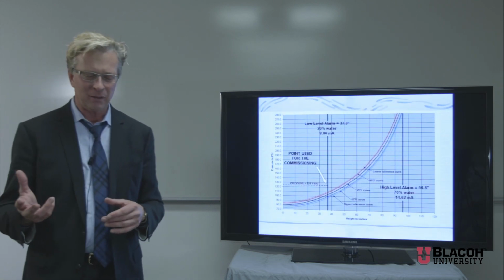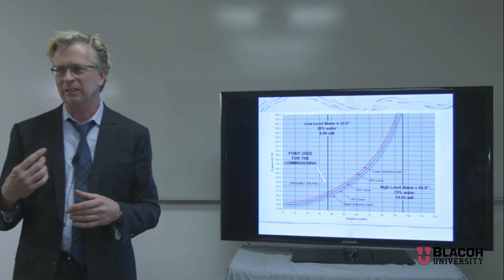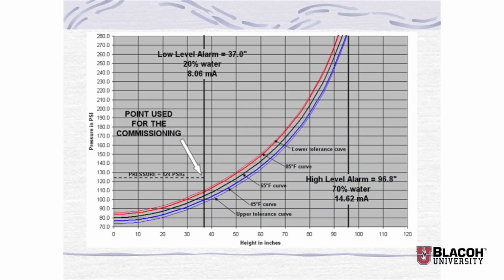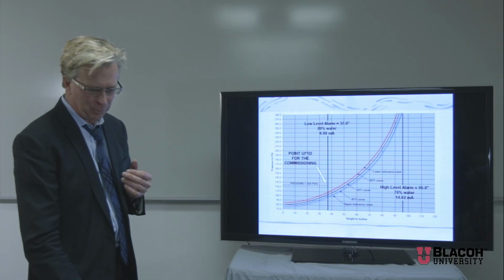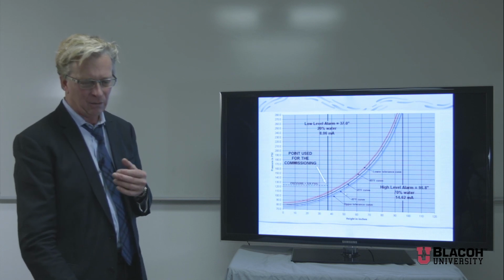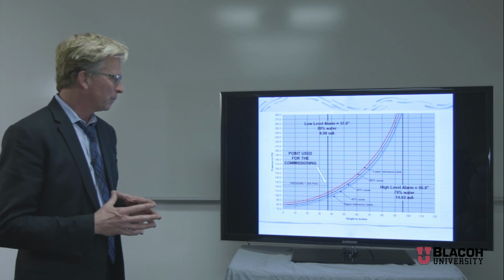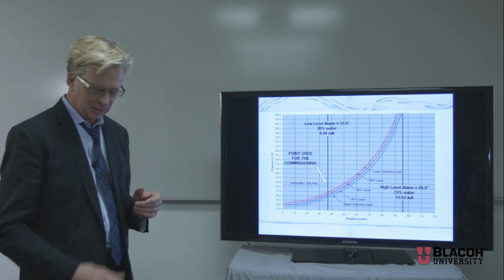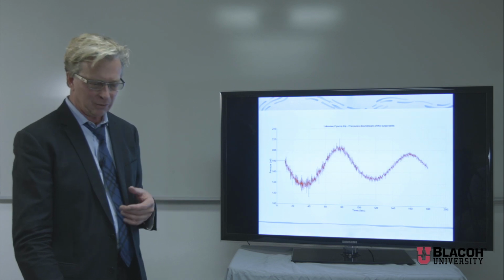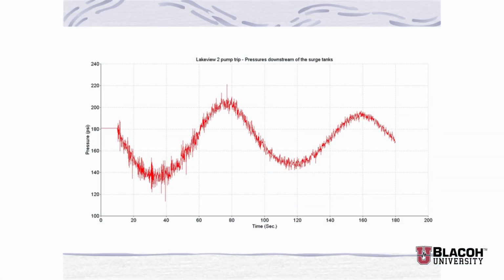We had talked earlier about the pre-charge pressure in the surge vessel, and compensating for temperature differentials in the system. So we look at the curve: ambient temperature in this area is 65 degrees Fahrenheit, and we look at the tolerances for the temperature where the surge vessel should be acting with a temperature differential. If we came out of scope, then our temperature is too low, and we might need to add some nitrogen, in this case, to the precharge pressure. But we can verify we know how we're supposed to operate and how we're supposed to be giving energy.